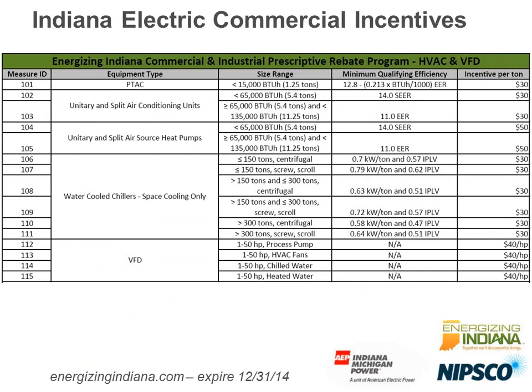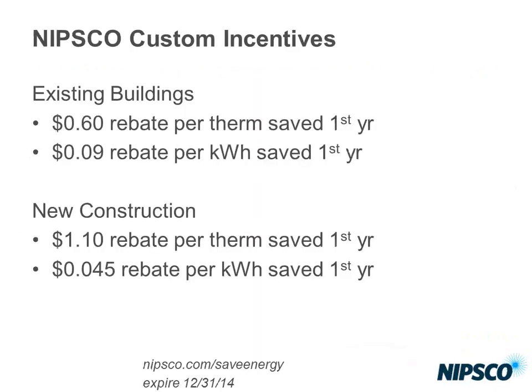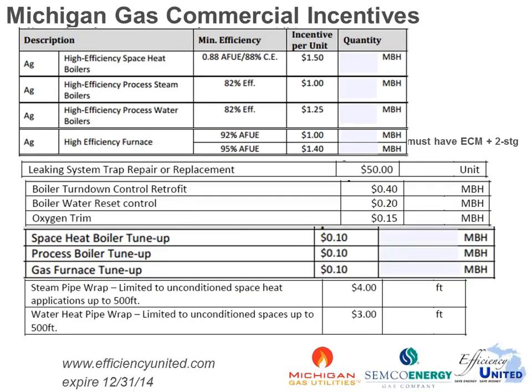So there are rebates for rooftops and split systems, for basically $30 per ton for either 14 SEER for small tonnages or 11 EER for large tonnages. There's also rebates for heat pumps at $50 per ton, PTAC. Chillers are $30 per ton. You have to hit a certain full load efficiency and a certain part load efficiency to get to $30. And then VFDs are $40 per horsepower for putting a VFD on a fan or a chilled water or hot water pump. The fan could be either a supply HVAC fan or a cooling tower fan or anything like that. There's also obviously custom incentives from NIPSCO as well for something else that's not on the list, like ERVs or VRF or something like that.